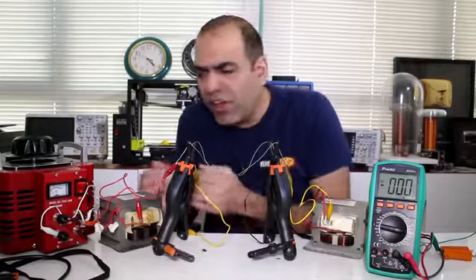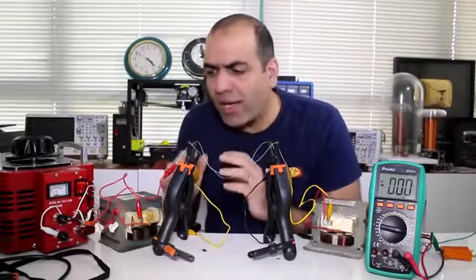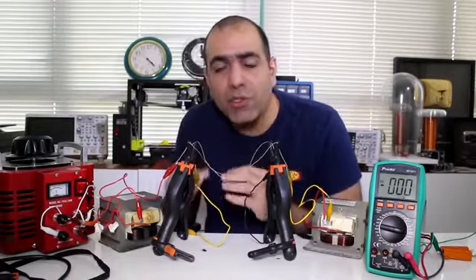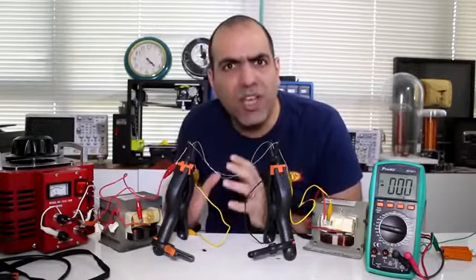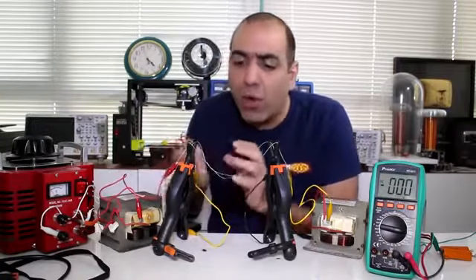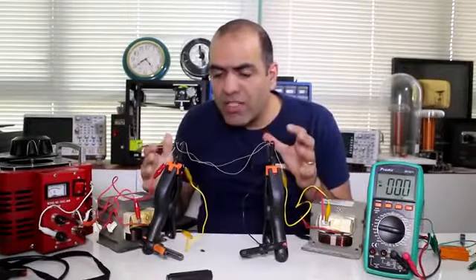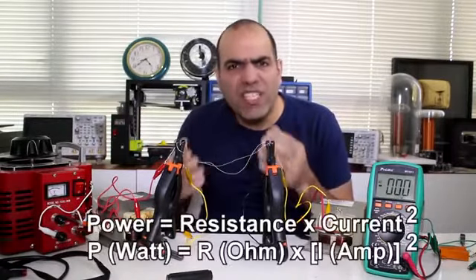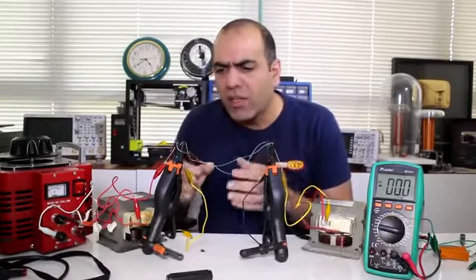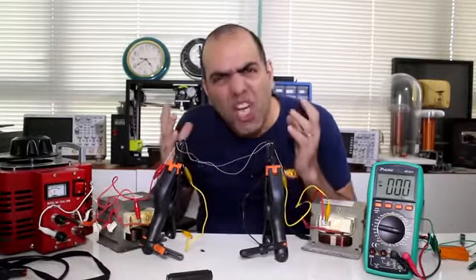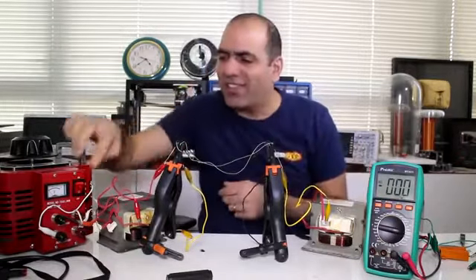So for example, if I increase the voltage by 20 times in order to have the same power, the current has to drop by 20 times at the output of the transformer and over the transmission lines. And because the power through a resistor is equal to resistance times current squared, the power would be 400 times less wasted on wires.